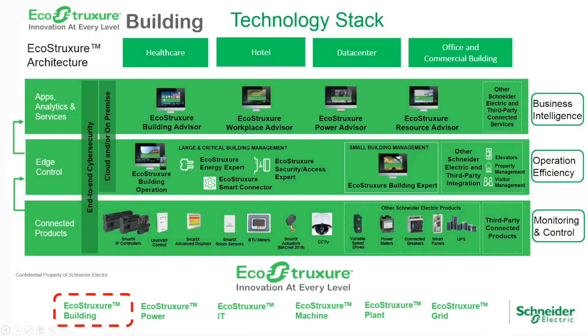What's happening now with the tech stack is we're re-envisioning the way buildings work. What used to be at the top level, the operator workstation, is now at what we call the edge layer, because we're connecting with field devices via BACnet over IP. So instead of that baud rate I mentioned before, we can connect to field controllers with Cat5 or Cat6 cable at 100 meg, whatever your internet connectivity is at home or your apartment.